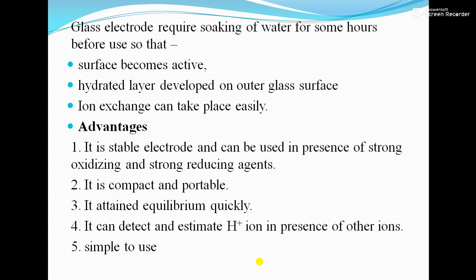While using the glass electrode, we have to soak it in water for one hour before use. The reason is that the surface of the glass electrode should become active. By dipping it in water, a hydrated layer develops on the outer glass surface, making ion exchange easier.